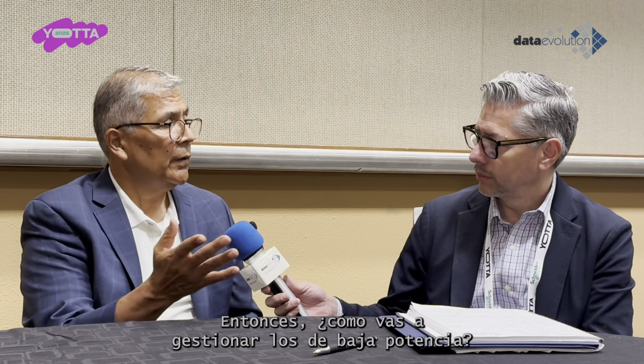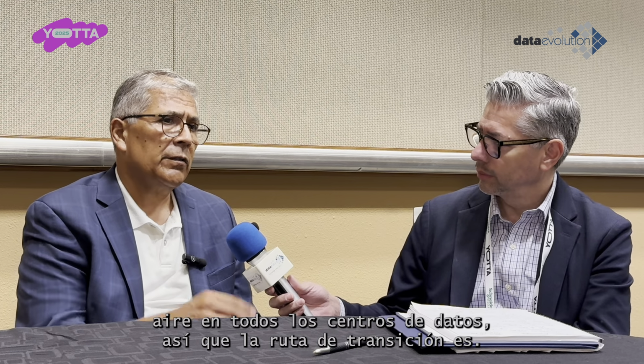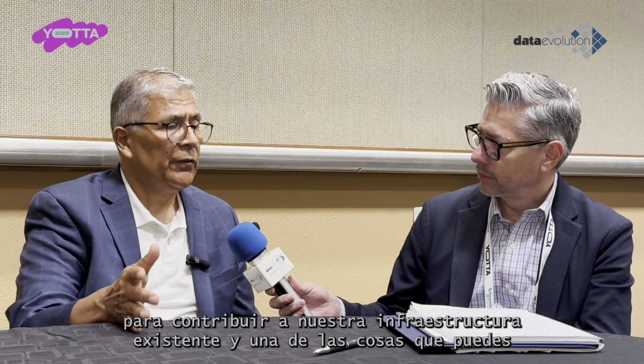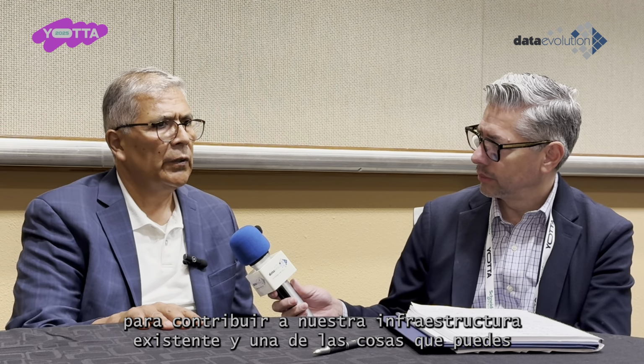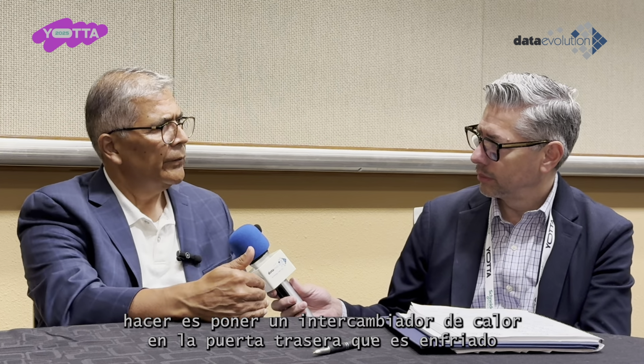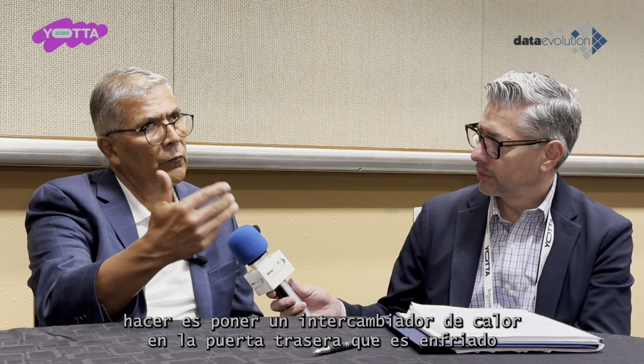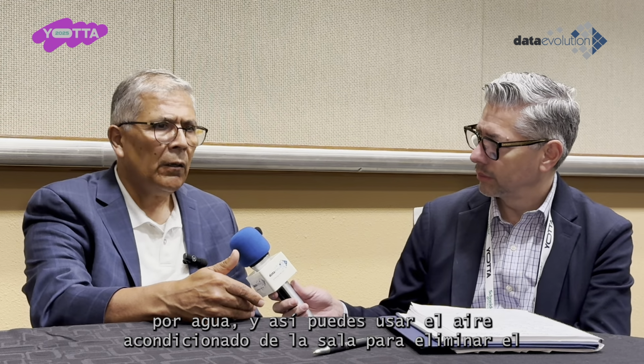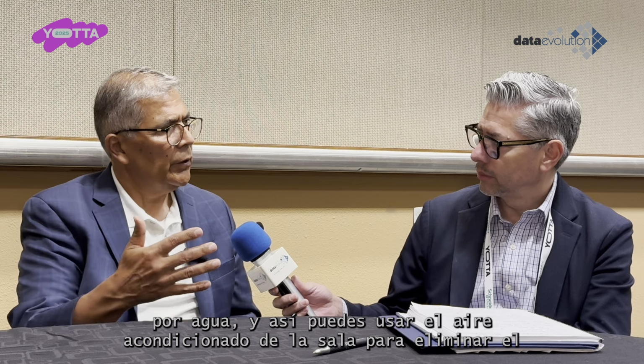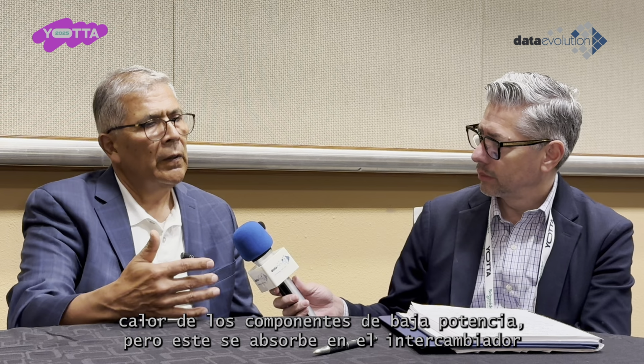The low power will probably be managed for a while with air, especially because we have air cooling infrastructure in all data centers. The transition path is going to be how we adopt two-phase or single-phase direct-to-chip in our existing infrastructure. One of the things you can do is put a rear door heat exchanger on the rack, which is water-cooled, so now you can use the room air conditioning to remove heat from the low-power components, but it gets absorbed in the rear door heat exchanger.